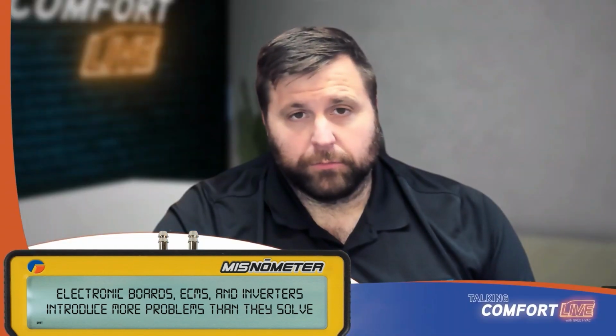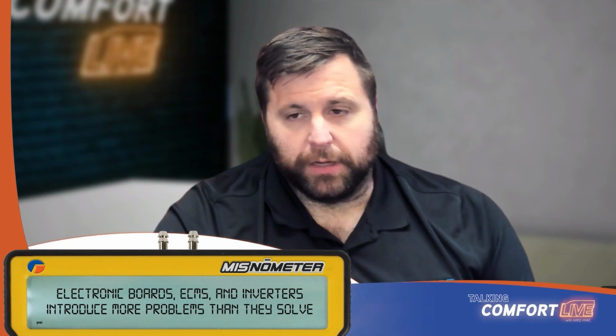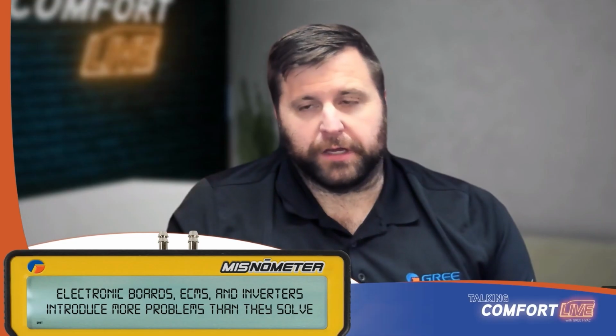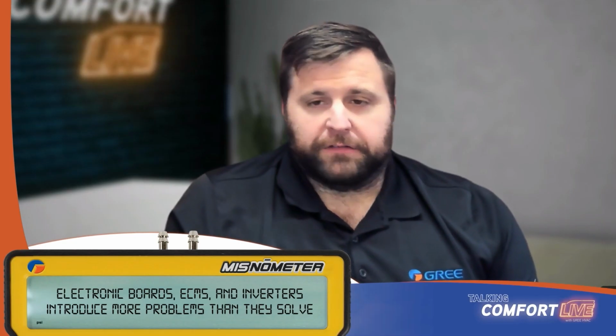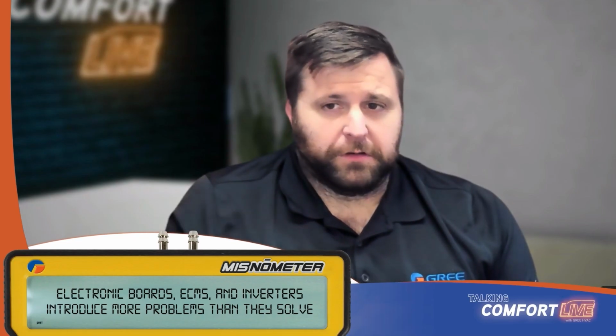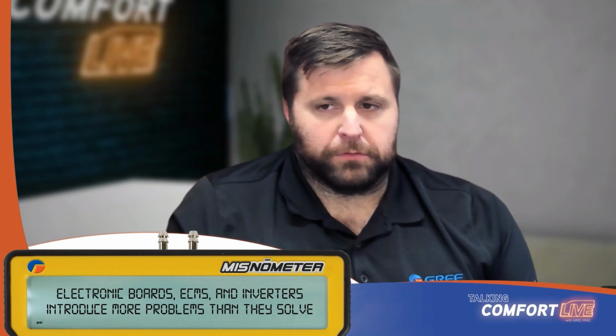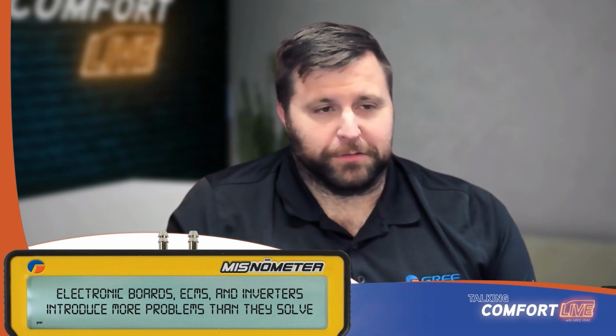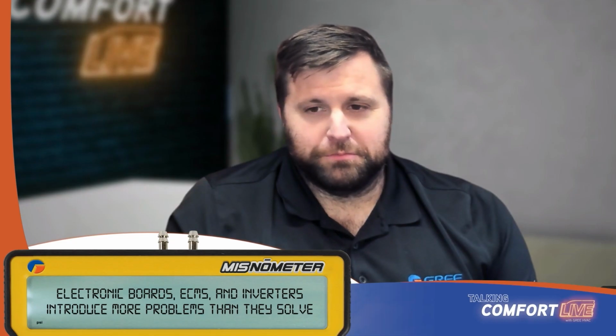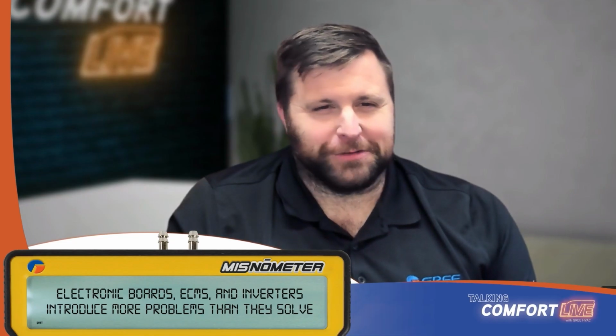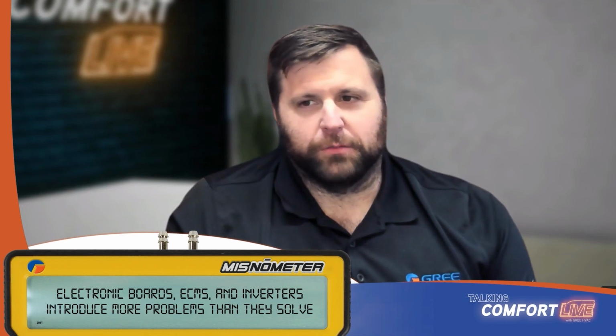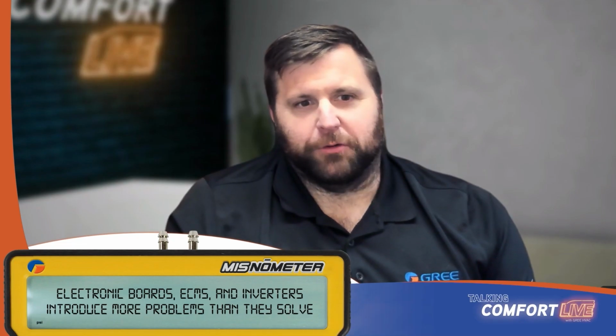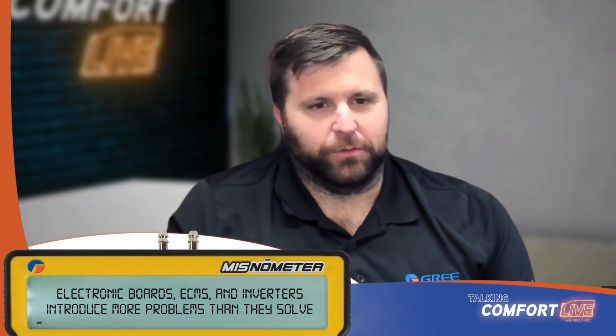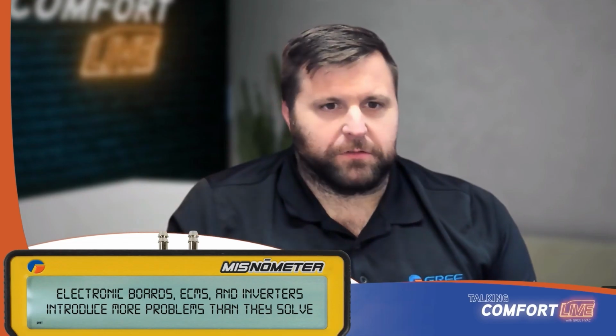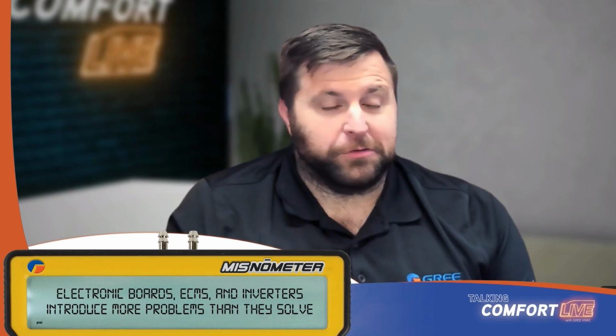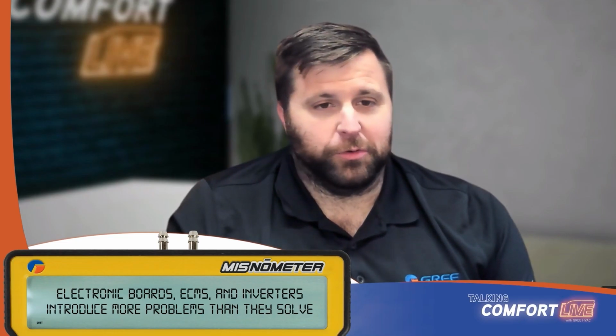Right. Well, luckily we've got methods for testing those boards. There's an example I like to use all the time in live classes where I just go through and describe basic inverter function and how you go about testing it. I like to use it every time I talk about something like that, unless it's a purely sales-oriented training or something like that. Because it is something that sticks with people, it's not just troubleshooting our equipment, it's troubleshooting anything that's got an inverter board. Real basic checks, like checking the DC voltage, the DC bus bar voltage. It's got capacitors, like every other motor's got. That's the method you're using to check those capacitors.